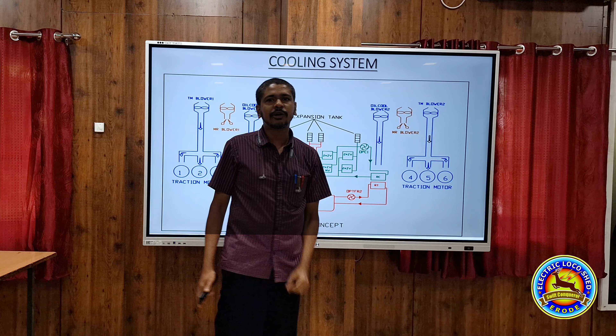All these motors are 3-phase motors. But previously, in the initial design of the WAP7 locomotive, the machine room blower was given single phase supply only. So we may wonder how single phase supply can run a 3-phase motor. For that, a split phase concept is used, with capacitors and timers introduced. Many people may have seen messages like 'machine room capacitor blower not open' while analyzing data or during PPO checking, because the previous design used a capacitor split phase concept to start the motor, after which it runs continuously — because it was driven by single phase supply.